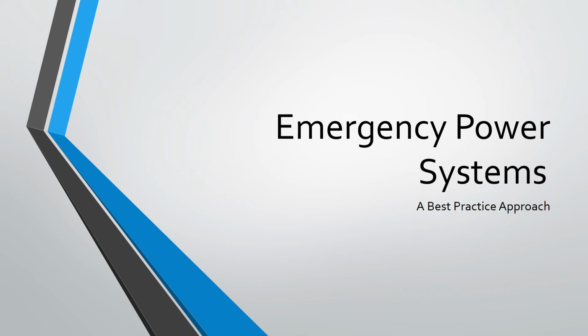And also, in some cases, you may lose a generator. Let's say you have 3 generators, 2 primary that you need, and a third is sort of an N+1 design, so it's a backup in case one of the 2 fail. Well, in an extended outage, you could lose, let's say, 2 generators, and you're down to 1 generator. Well, you're going to want to load shed, and you're going to want to have the ability to take things offline. And again, sometimes manual switches are designed for that.